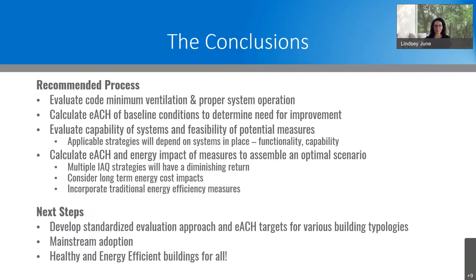So to conclude, the optimal process for determining an energy efficiency IAQ strategy is to start by determining if spaces meet code minimum ventilation requirements and inspect systems for proper operation and make adjustments as necessary, such as outside and return air dampers are functioning correctly, or ERVs are not cross-contaminating airstreams. The ASHRAE Epidemic Task Force documents have guidance for system evaluation. NYSERDA also developed an IAQ best practices guide for colleges and universities that's posted on the IAQ website that has a systems evaluation checklist based off of ASHRAE's guidance documents. And this is also applicable to other commercial sectors.